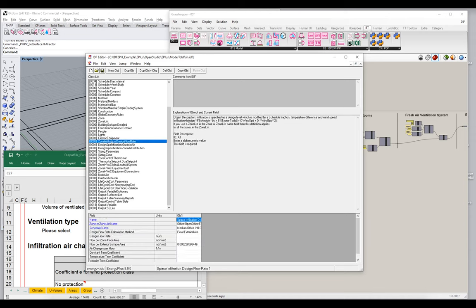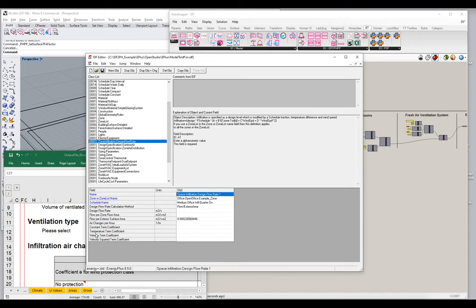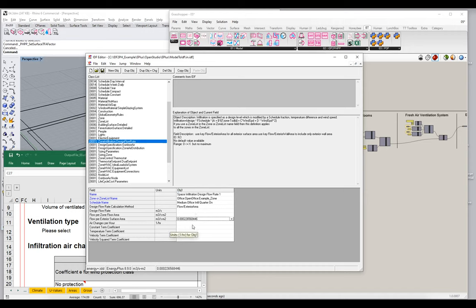Looking for 3.77 ACH — I don't have it directly. Instead, what I have is this airflow per exterior surface area in cubic meters per second per square meter, which is a weird little tiny number. I also have a design flow rate calculation method and a schedule. This is a very different input unit than the PHPP, and the notion of using a schedule to calculate the infiltration air exchange is very different from the PHPP approach.